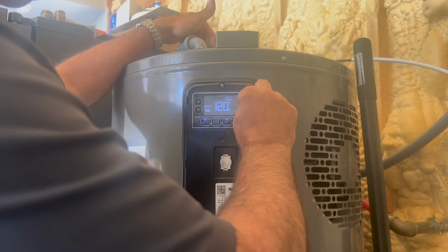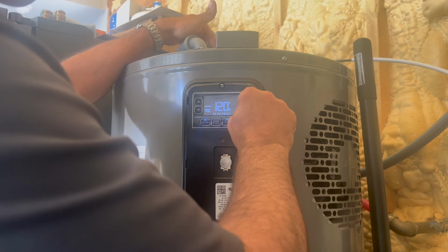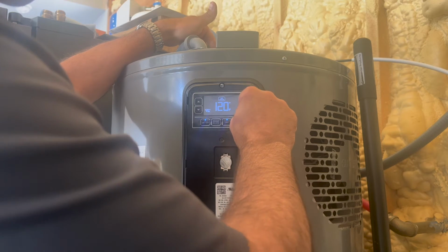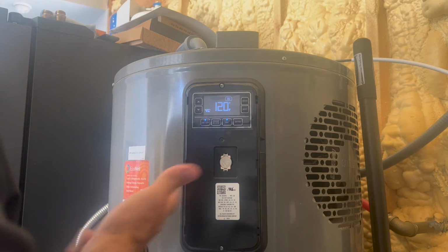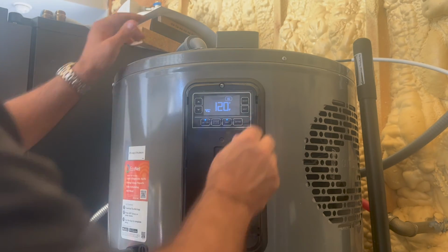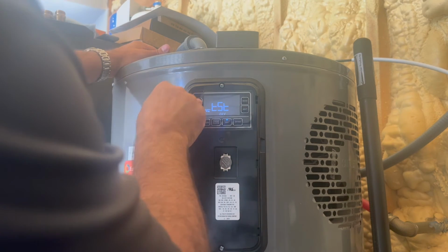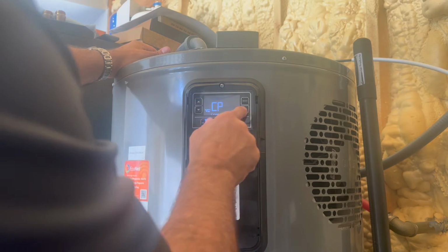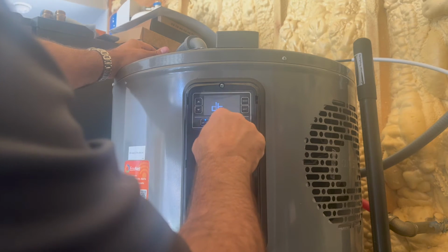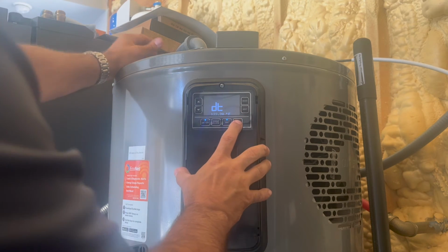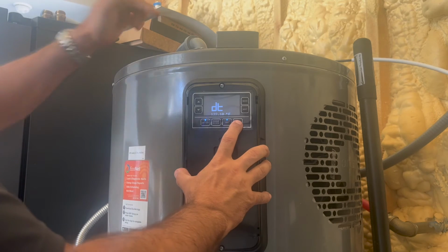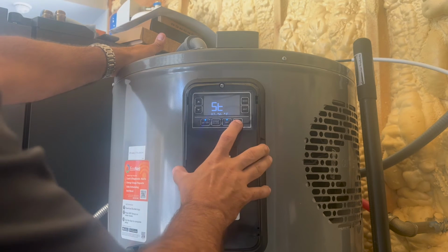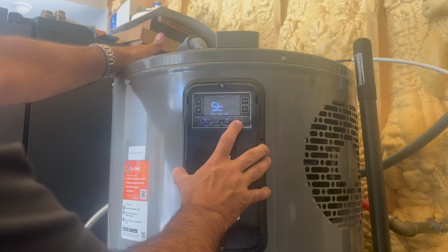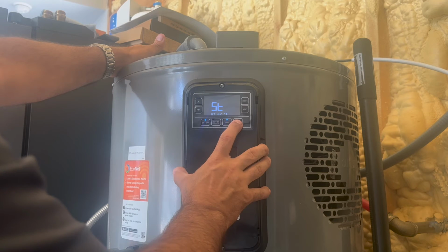I'm gonna leave all this in here because if you're trying to do this or you're trying to direct somebody to do this, this is frustrating. All right. Enter compressor. Let's see what we have. Discharge temp is 122. We're trying to get our water to 120. That's definitely going to do it. Suction temp is 83. We got almost a 40-degree split between discharge and suction. And we've got our test going again.